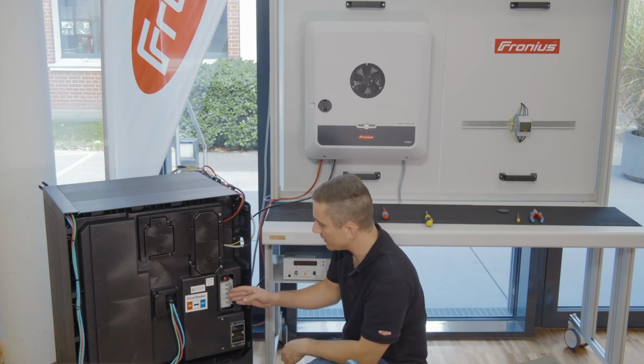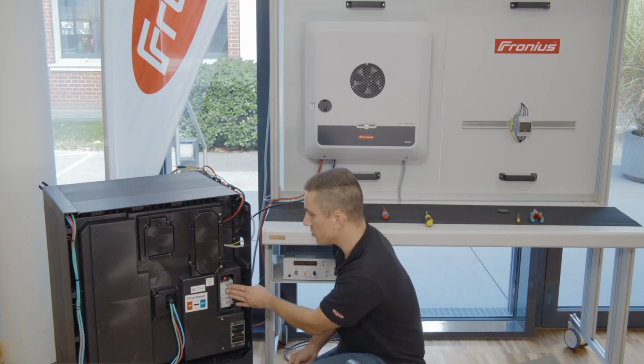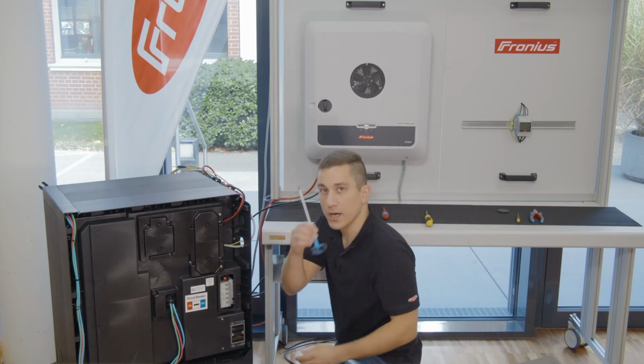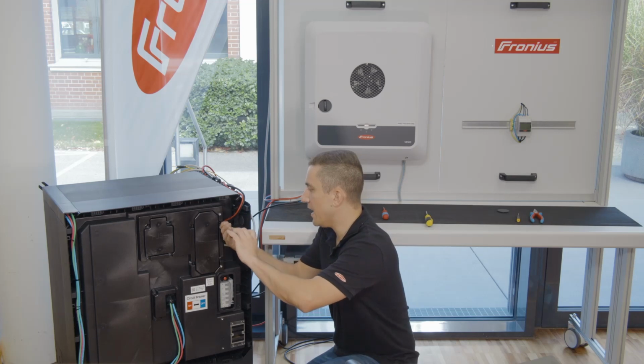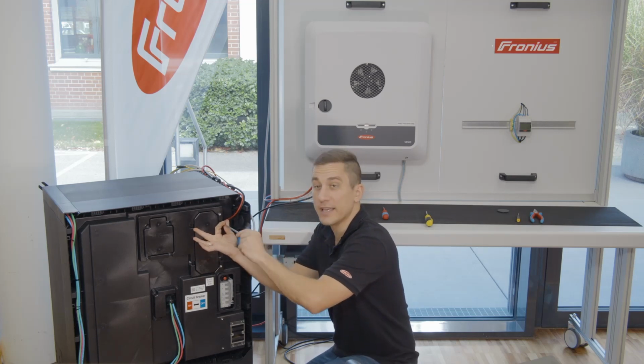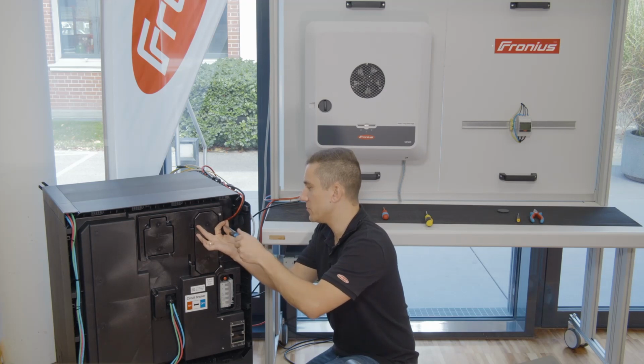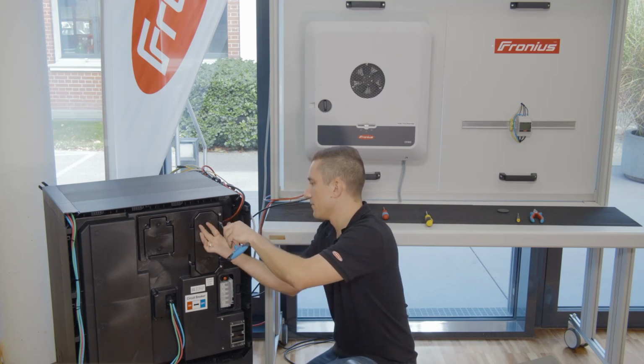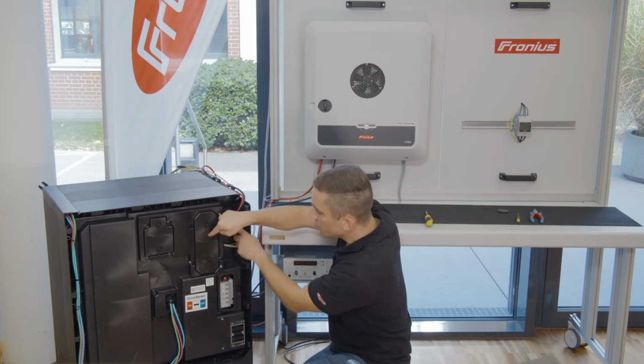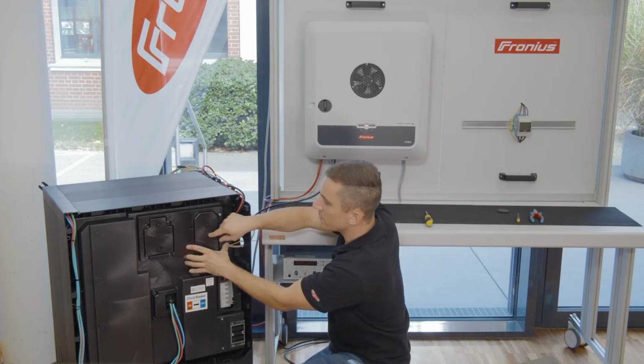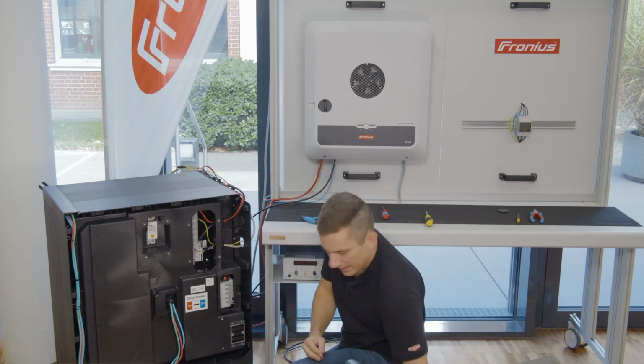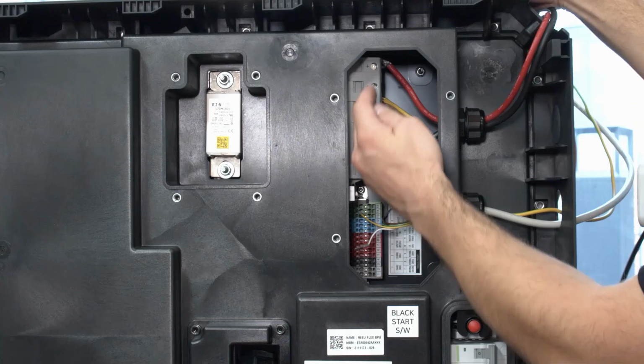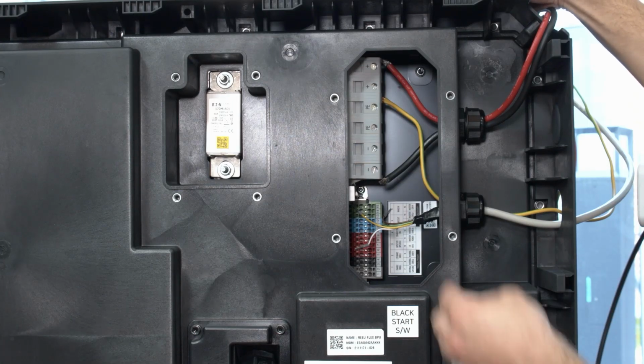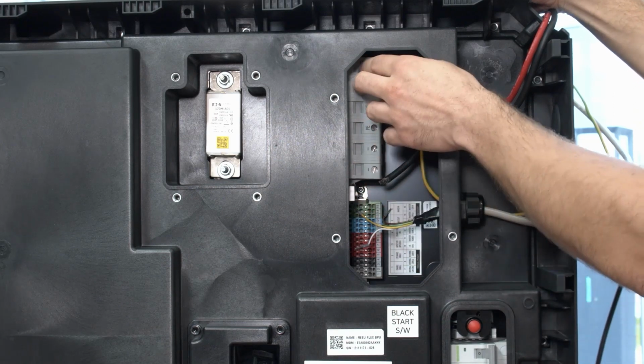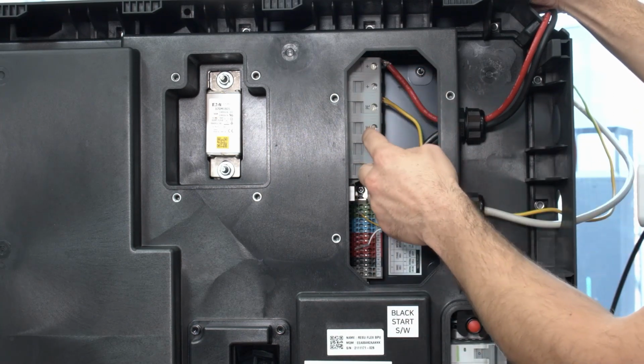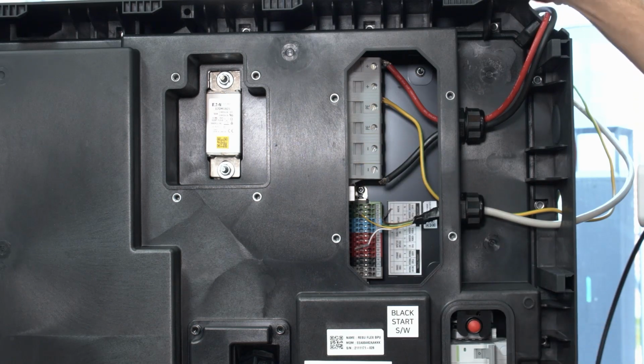So after making sure that the circuit breaker is in the off position, you can use your Torx device and open up the cover for the DC and data communication area of the LG battery system. After removing the screws that you can see here, you can remove the cover. And down below we see the DC cabling of the battery system. You have two minus poles and two plus poles here, and in the middle you can see the protective earth cable.